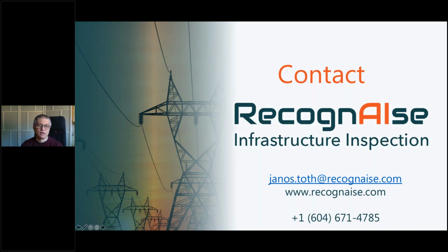Let me give you a bit of background. Magnetic imagery is carried out particularly with robots crawling on conductors, checking the steel core and the steel core zinc coating thickness using eddy current. This basically checks the conductor core condition, and also the zinc thickness, which could indicate the remaining life of the conductor, and if zinc coating is left, how much steel core remains. Because when the steel core has direct attachment to the aluminum, corrosion is highly accelerated. Some utilities consider that when the zinc coating is gone, the conductor has to be removed and replaced.